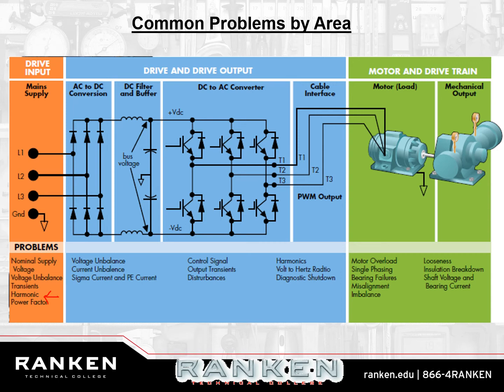Again, less than 100 horsepower, we're just going to say the drive is junk, and we're going to pitch it and get another one. For the most part, that's all we can do. By the time we try to troubleshoot one of these little drives, if you can even access the parts with the little drives to check them, you're not going to have a lot of success.